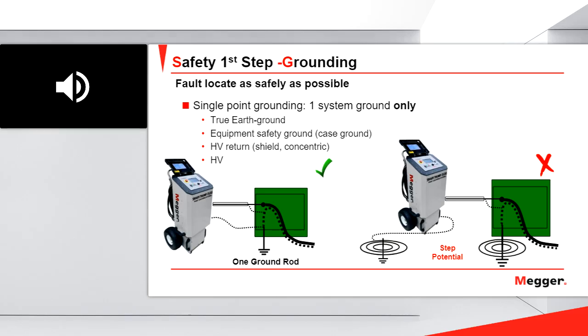If you see the picture on the right, you will see that in this case I have the safety ground connected to this rod, but the metallic shield, the concentric of my faulted cable, is connected to another rod. So if it happens that I am in the middle, I could suffer a step potential. This is what happens when I don't have a single point grounding. Okay, so that is also very important to keep in mind. When you do fault location, always look for a single point grounding.